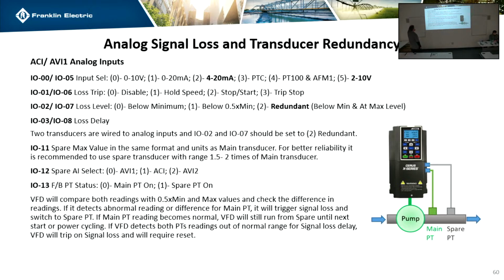Here's the signal loss and transducer redundancy setup. It's all in the I/O group. So if you're ever going through the drive, the I/O is the inputs and outputs. Everything for inputs and outputs is in the I/O group. I can send you guys a PDF version of this presentation if you want, so you guys can copy all this stuff if you ever actually need to set this up. But it'll go through everything.